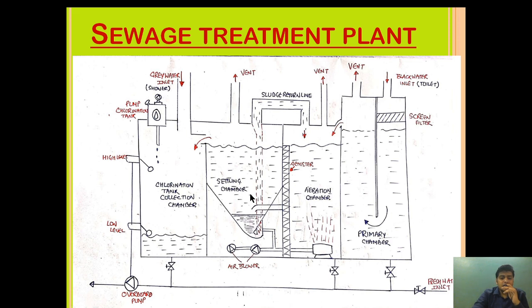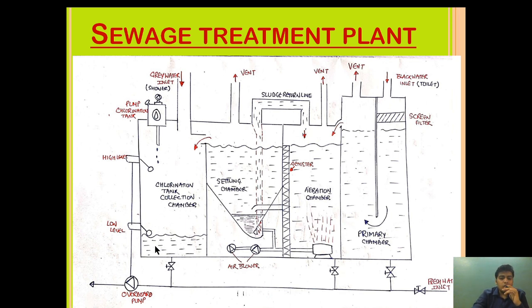After the settling chamber, full disintegration and decolorization of the sewage is carried out. The treated effluent then overflows to the collection chamber, where a chlorination pump adds a small dose of sodium hypochlorite drop by drop to disinfect the treated sewage. After a short storage period, it is discharged overboard by an automatically operated, level-operated overboard pump, once it is confirmed the ship is three nautical miles away from land and en route.